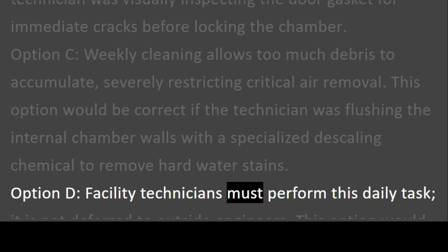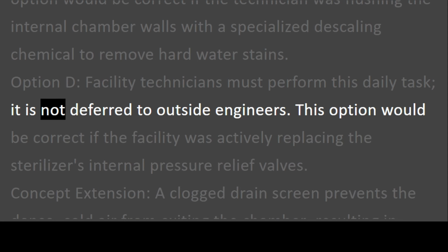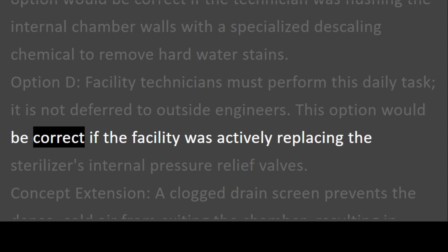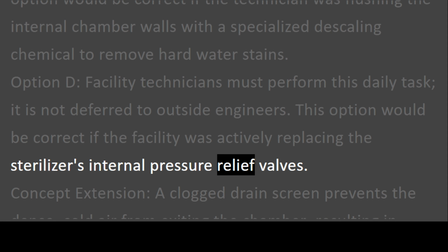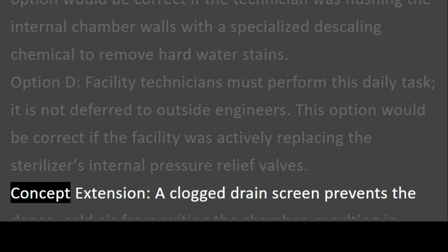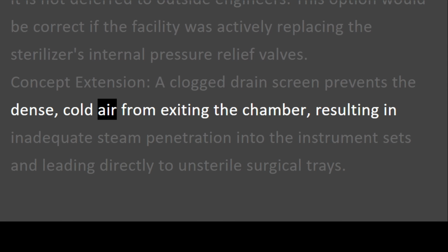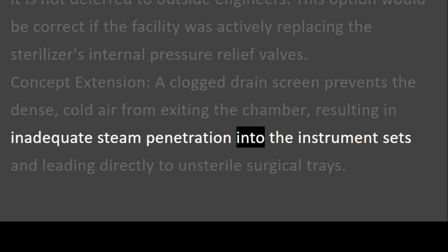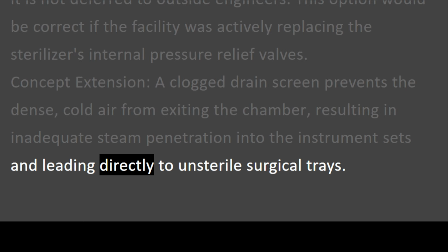Option D. Facility technicians must perform this daily task. It is not deferred to outside engineers. This option would be correct if the facility was actively replacing the sterilizer's internal pressure relief valves. Concept extension. A clogged drain screen prevents the dense, cold air from exiting the chamber, resulting in inadequate steam penetration into the instrument sets and leading directly to unsterile surgical trays.